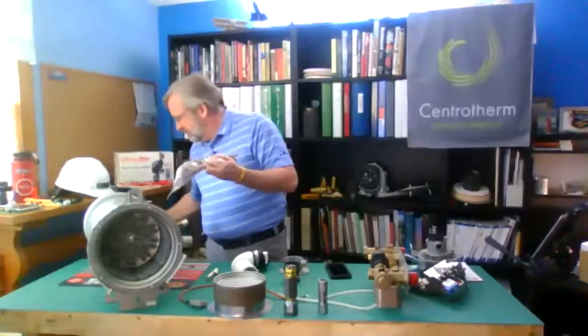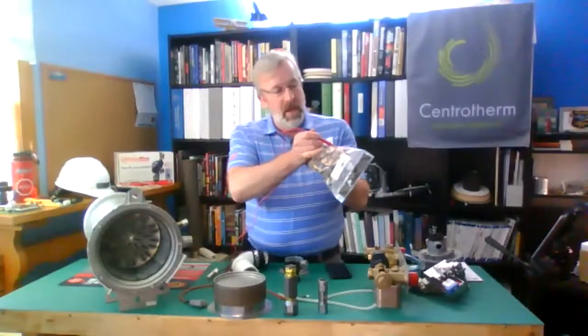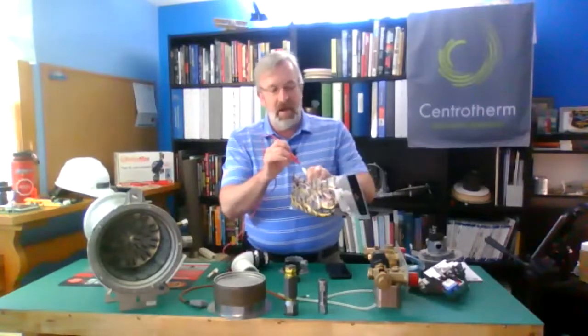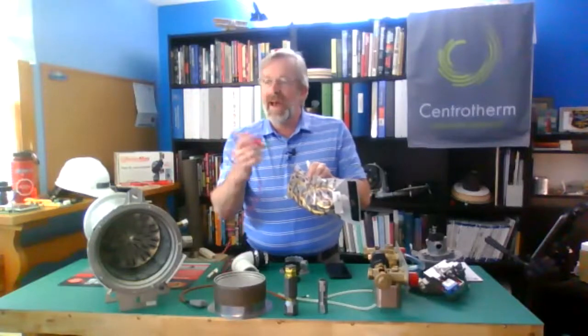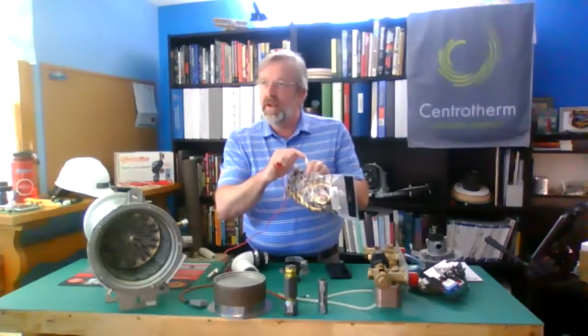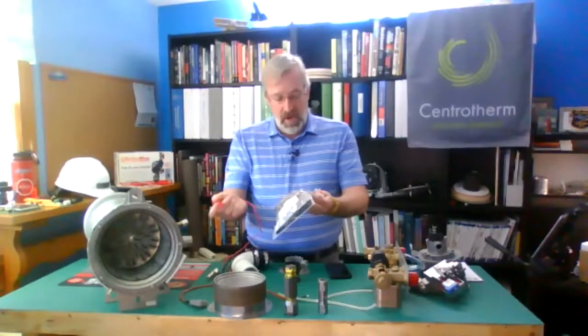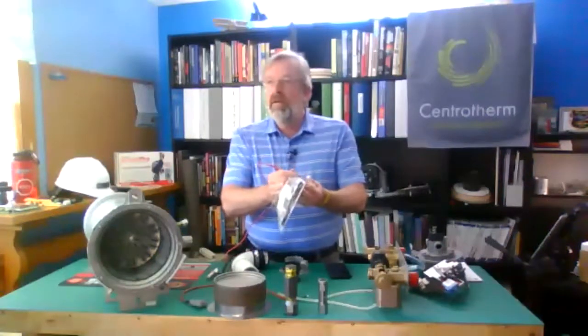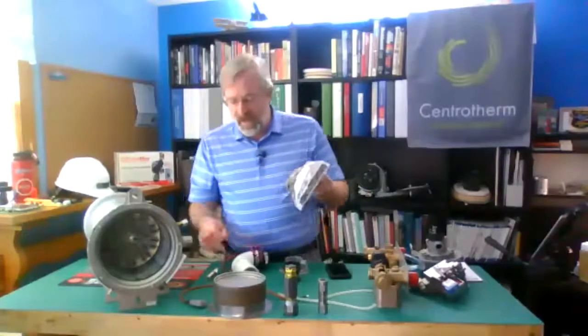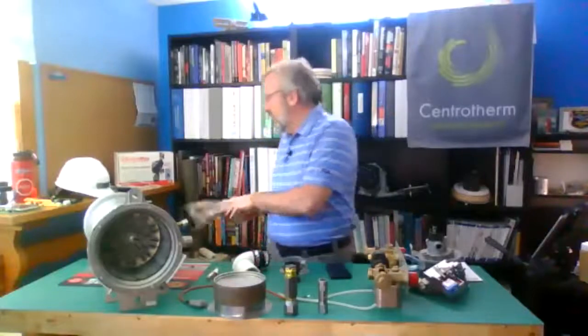there she is. Take the pin on your multimeter and reach it in from the back side. The reason we reach in from the back side is if I put it in here, the end of my multimeter is actually larger than the pin diameter, and I can stretch that out. Then when I go to plug it back in, it doesn't work. So what I really want to do is slide it in here from the back, set it there, go through and fire again, make sure I get 24 volts on it. But always check it from the outside of the Molex plug, not the inside. That also allows you to leave it connected. So you're really getting a true test of, do I have enough?